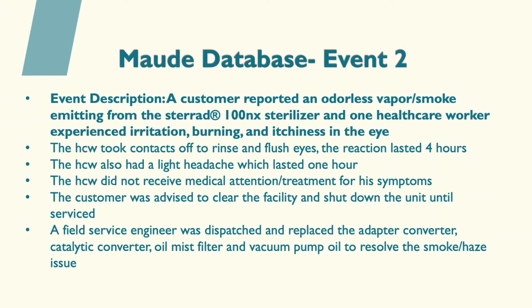I have another example here. Now this was a different one, this was a STERRAD. A customer reported an odorless vapor or smoke. And the healthcare worker experienced irritation, burning, and itchiness of the eyes. He took off his contacts to rinse and flush his eyes. The reaction lasted 4 hours.